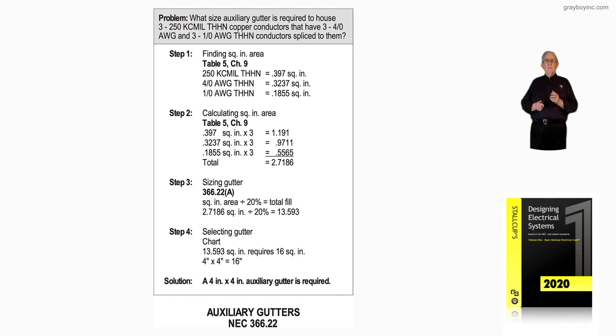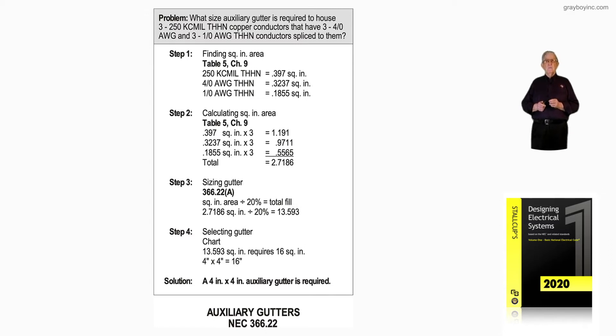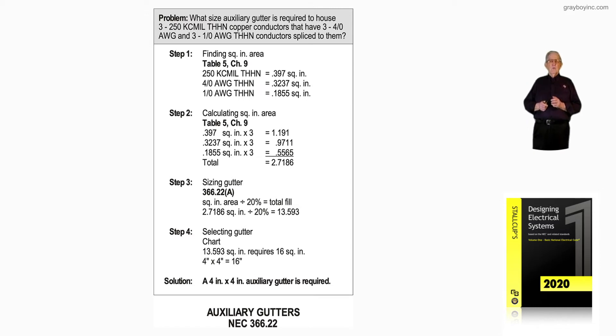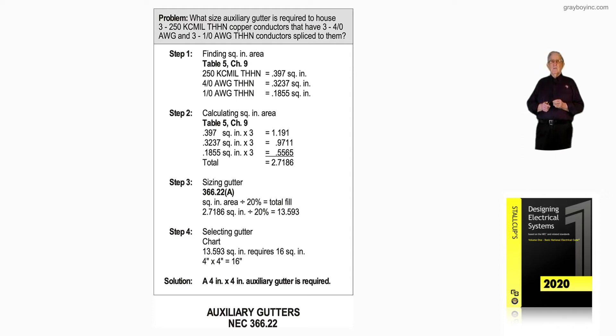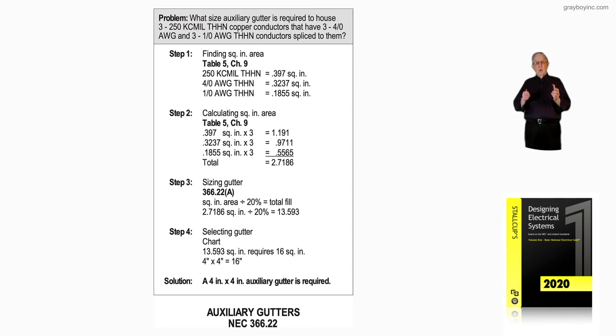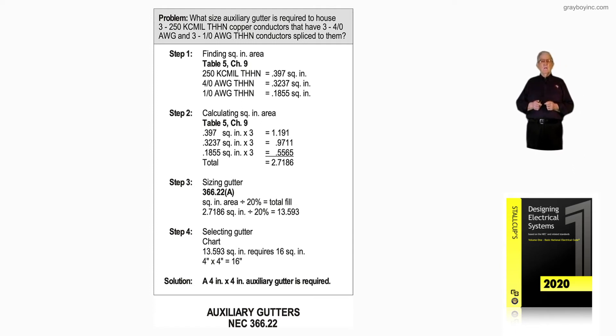We're wanting to size an auxiliary gutter to house three 250 KCMIL, which is the feeder, three THHN copper conductors, three 4/0, and three 1/0 THHN conductors spliced to the larger conductors using the splicing rules of 240.21(B).